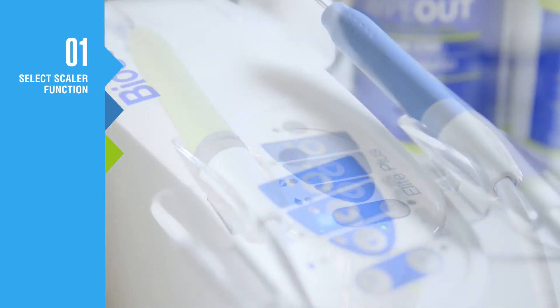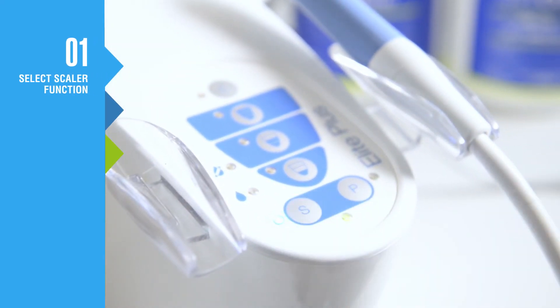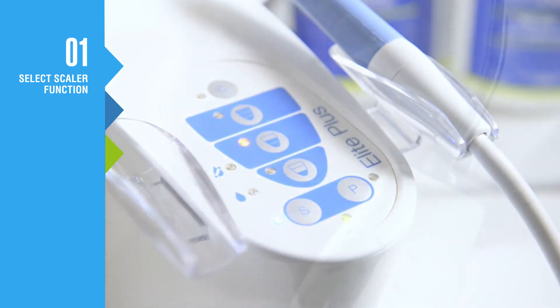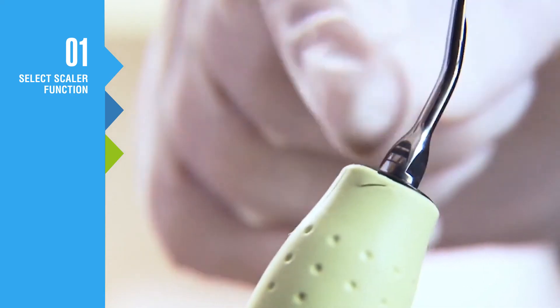With the unit in standby mode, press the S button to enter scaler mode. Select the working mode, one, two, or three, that matches the number on the base of your selected scaler tip.